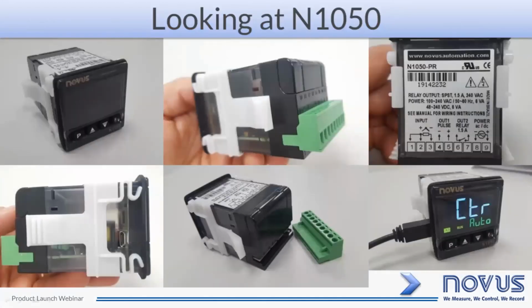So now let's see how N1050 looks like. It is 48 by 48 or 1/16 DIN format. It has detachable connector. Its USB port is on the left side. It can be powered and configured just plugging in the USB cable. The enclosure is slightly transparent. The frontal keys are made of silicone rubber. The frontal panel is very thin and it's IP65. The label on the top shows all relevant information of the controller, including wiring diagram, serial number, and approvals.